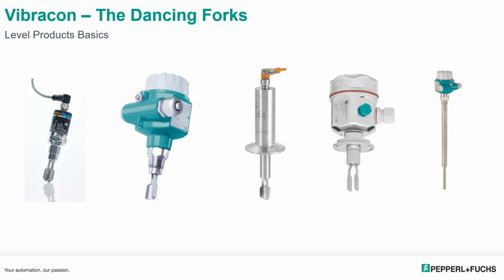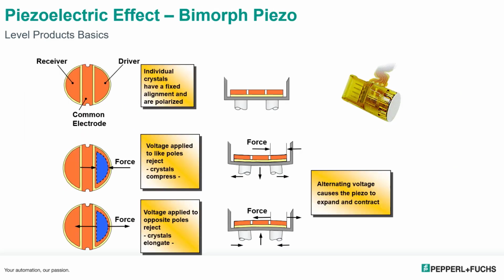These are basically vibrating forks that will dampen when the medium reaches the fork lengths. The Vibracon works with a piezo element in the bottom where the forks extend out. And we actually exercise this crystal so that it vibrates, and it vibrates at a certain frequency. When the medium reaches a certain level inside the forks, it dampens that frequency and we get a shift in the frequency, which we detect and give as an output.